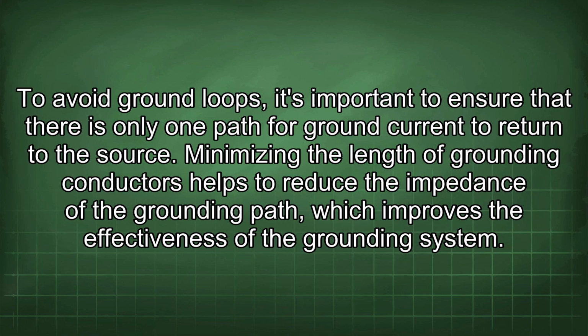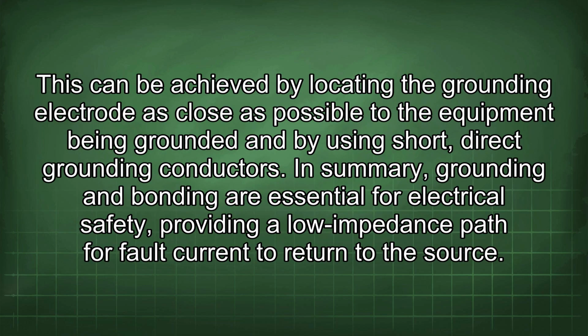To avoid ground loops, it's important to ensure that there is only one path for ground current to return to the source. Minimizing the length of grounding conductors helps to reduce the impedance of the grounding path, which improves the effectiveness of the grounding system. This can be achieved by locating the grounding electrode as close as possible to the equipment being grounded and by using short, direct grounding conductors. In summary, grounding and bonding are essential for electrical safety, providing a low impedance path for fault current to return to the source.